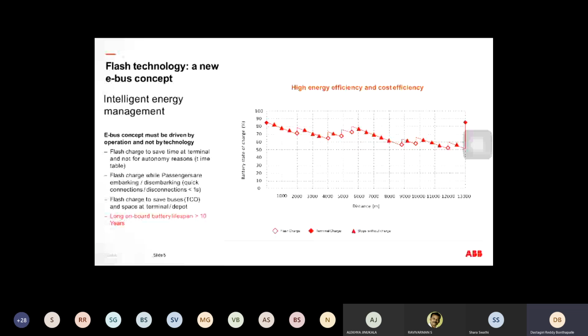Any battery has a rating called the C rate, which is the charge or discharge rate. For example, for a 100 ampere-hour battery, a C rate of 1 means in 1 hour you can take a maximum of 100 amperes at any instant. If the C rate is 2, that means you can discharge or charge 200 amperes.